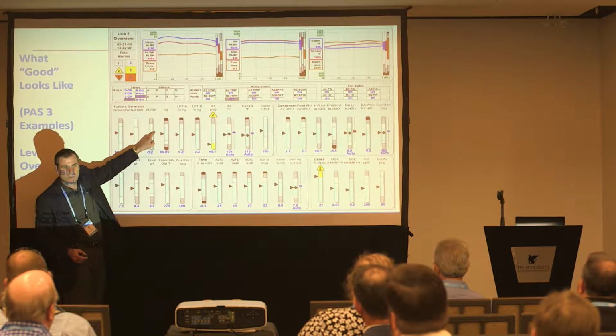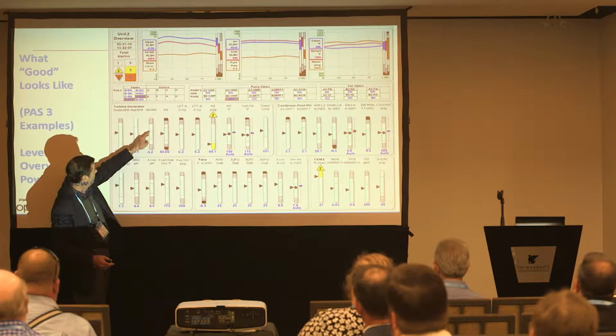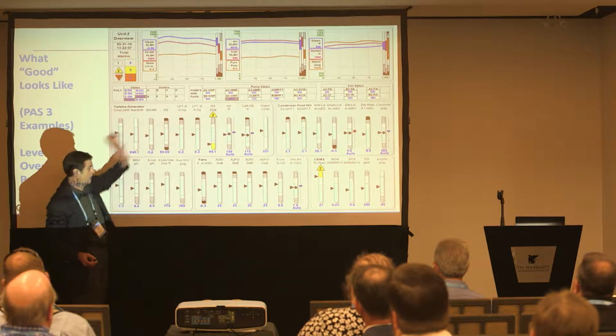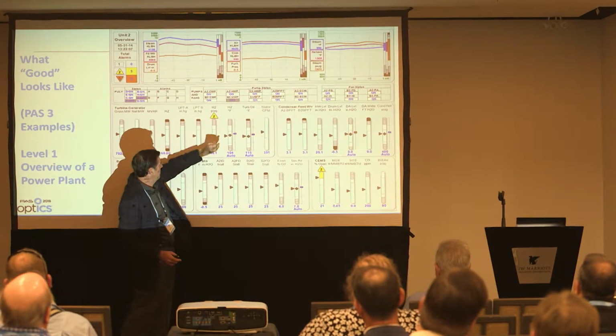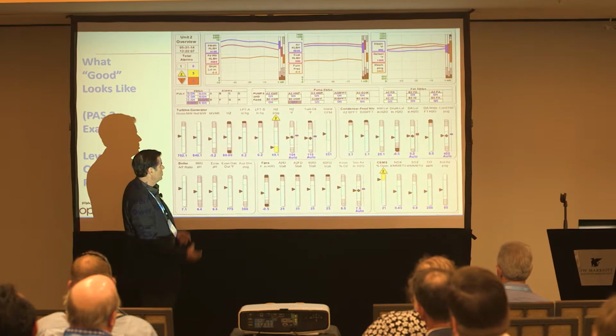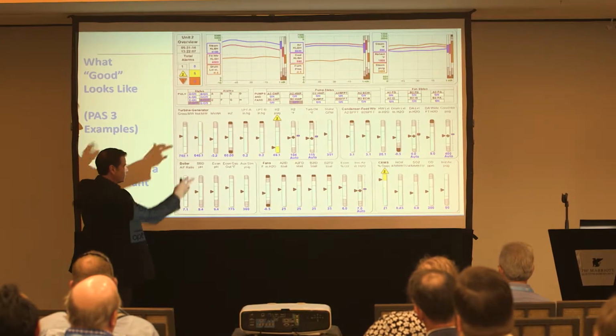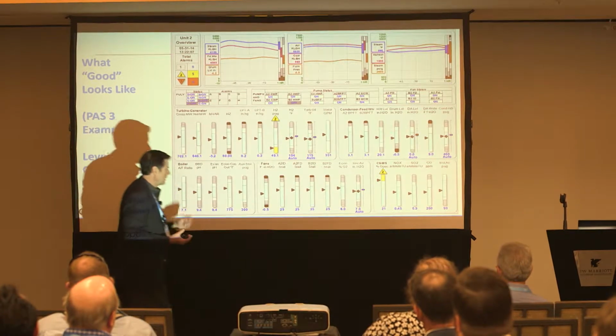This little 1 pixel line is very important. It's the edge, and you can tell when the pointer gets close to the edge. And so the alarm comes in, a separate redundantly coded alarm indicator appears, it brings your attention to it, and so forth. All right, so this is an example of using analog indications to provide context.